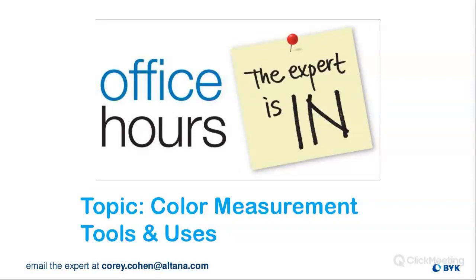Okay, got one from Ashley here. How comparable is sphere geometry to the 45-0? Can they be used similarly? Is there a quantifiable deviation between measurements with both of these instruments? With higher gloss levels, you're going to see larger deviation. So generally, we recommend using the same geometry if you need to compare measurements with a supplier or a customer.